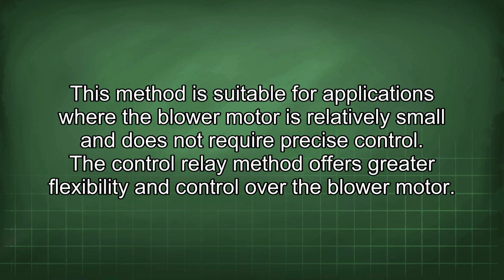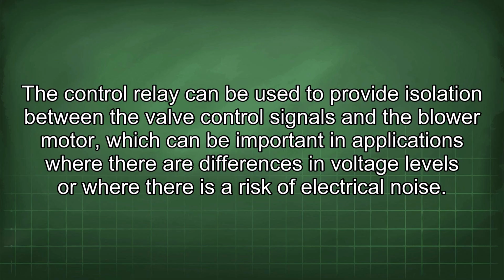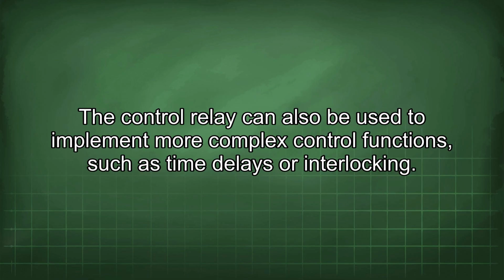The control relay method offers greater flexibility in control over the blower motor. The control relay can be used to provide isolation between the valve control signals and the blower motor, which can be important in applications where there are differences in voltage levels or where there is a risk of electrical noise. The control relay can also be used to implement more complex control functions such as time delays or interlocking.